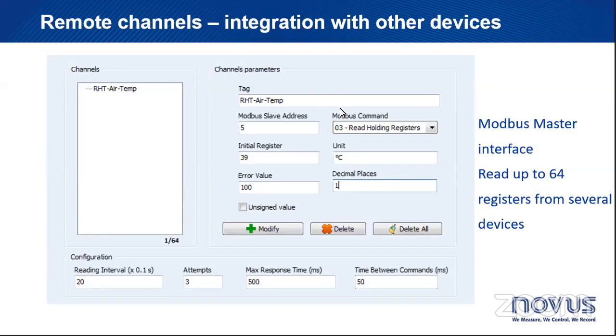Okay, but how do I do that? Well, connecting IO modules to its RS-485. So that means you can expand its channels by up to 64 channels. Okay, so if I wanted to have 64 analog inputs, I would be able to use the 8 that are native on the FieldLogger, and I will use 56 remote channels, and that will allow me to have 64 analog inputs. These will work for digital inputs. These will work for proper transmitters.